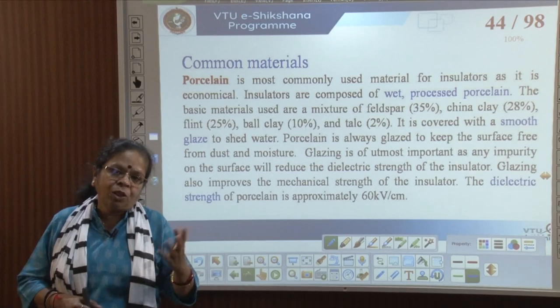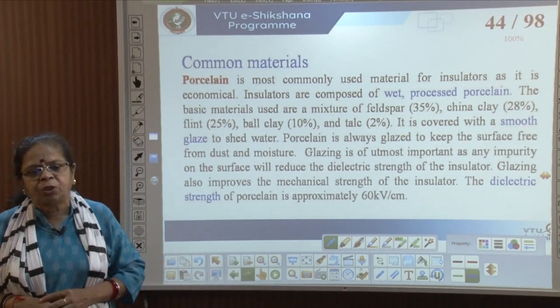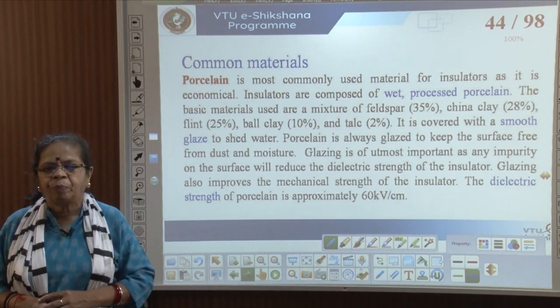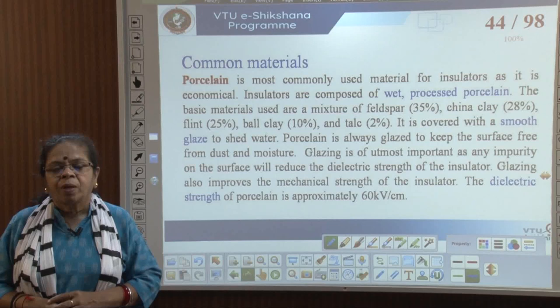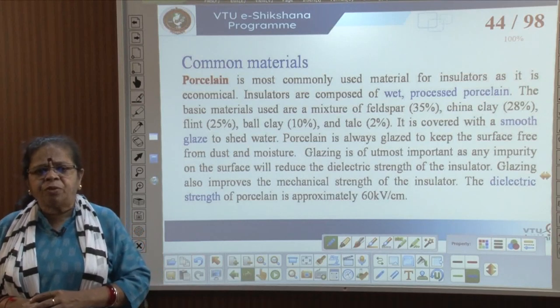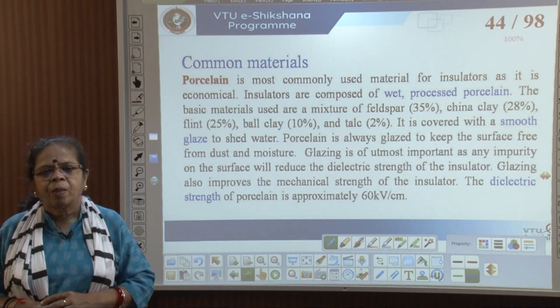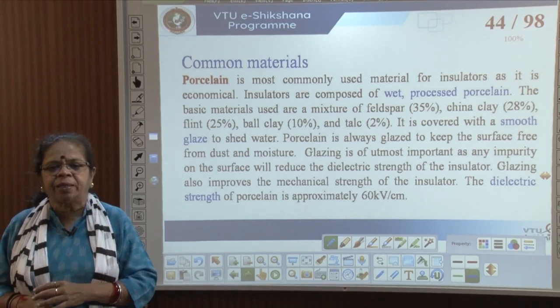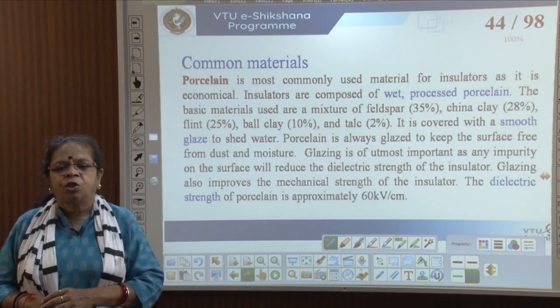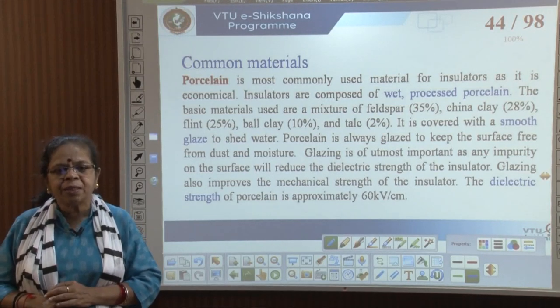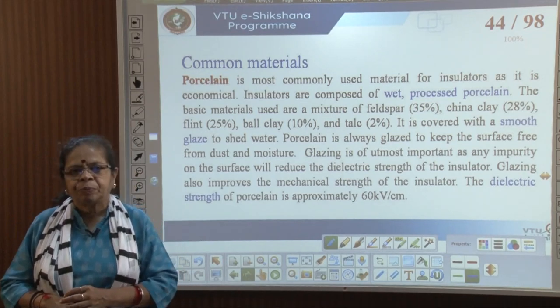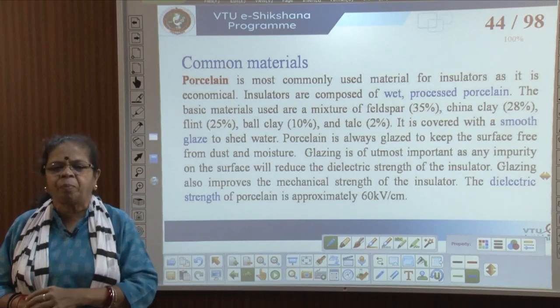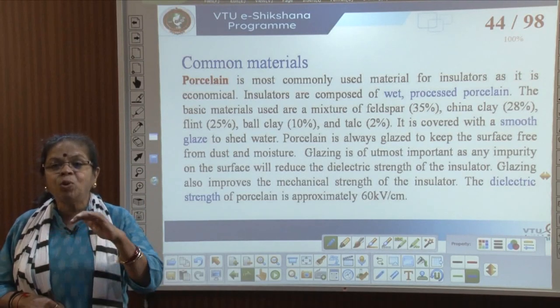The most common material used for insulators is porcelain — it is economical. Insulators are made from wet-processed porcelain; the basic materials used are feldspar, china clay, flint, ball clay and talc. All the insulators you generally see around are made of porcelain and are covered with a smooth glaze.